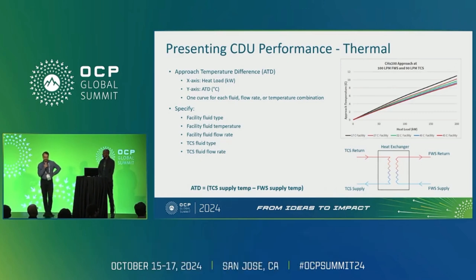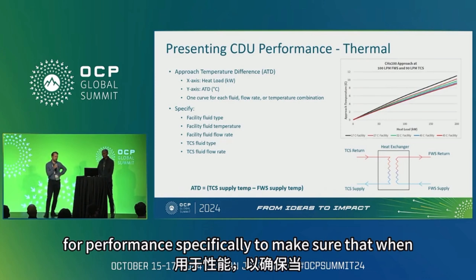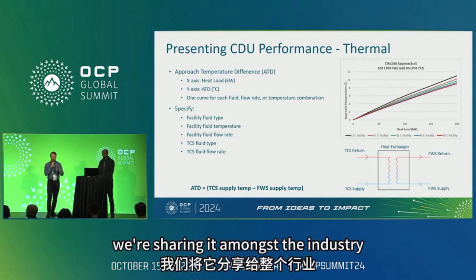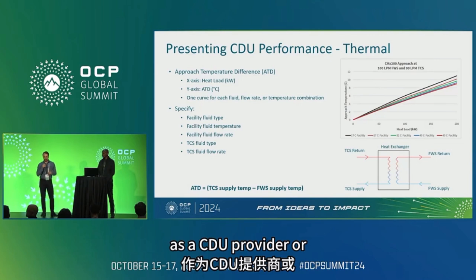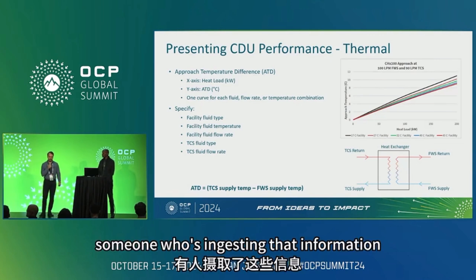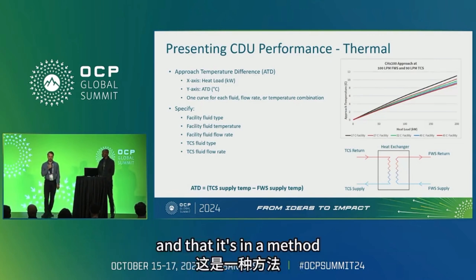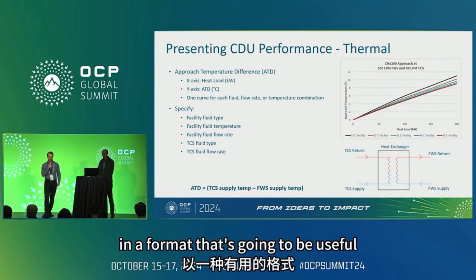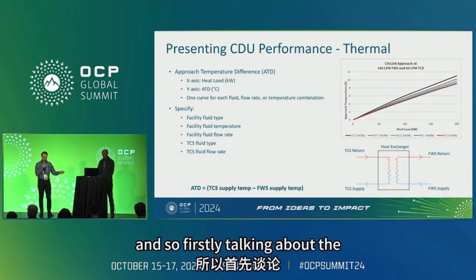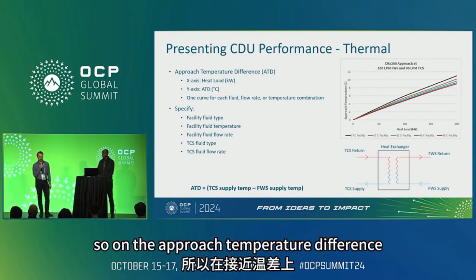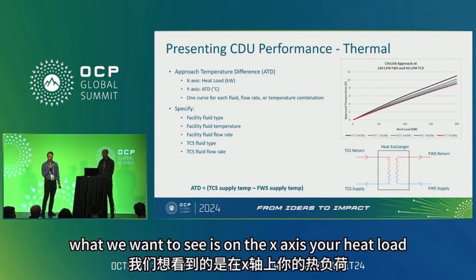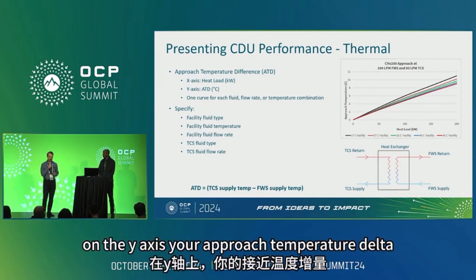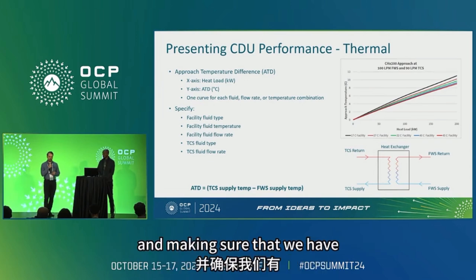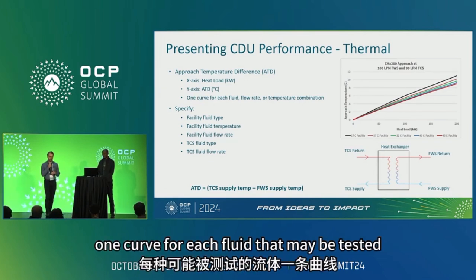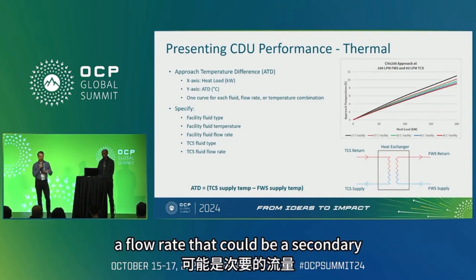So one other thing that we wanted to kind of highlight as well is just the way that we're presenting the data for performance specifically, to make sure that when we're sharing it amongst the industry as a CDU provider or as someone who's ingesting that information, that it's consistent and that it's in a format that's going to be useful.